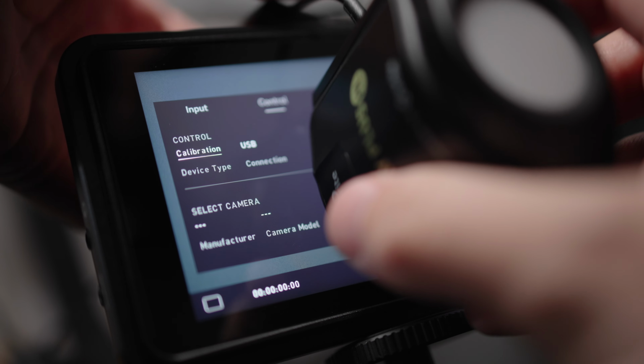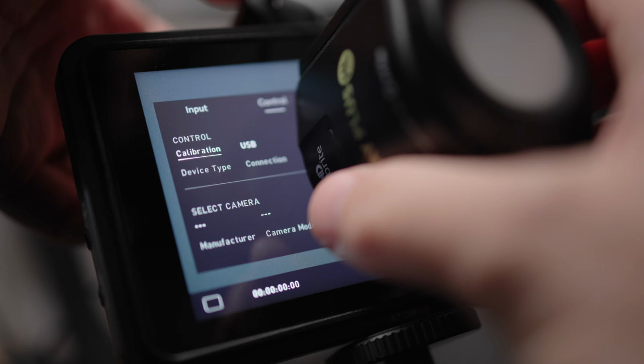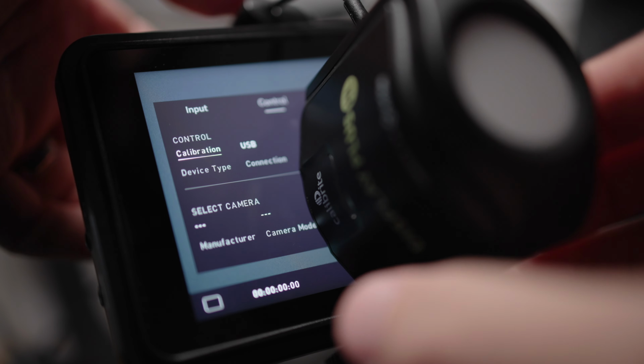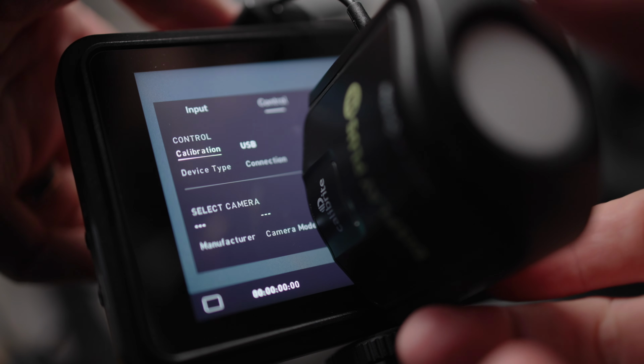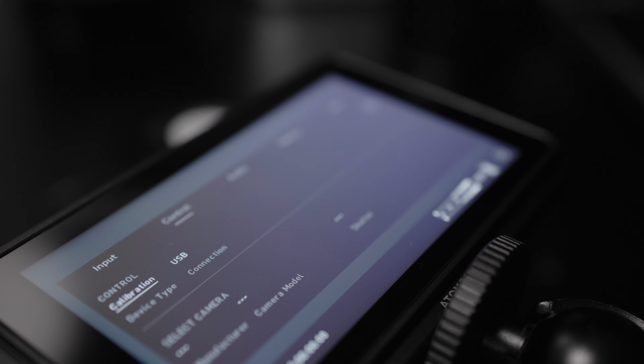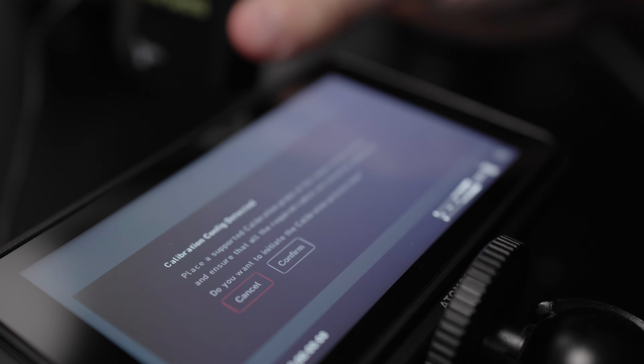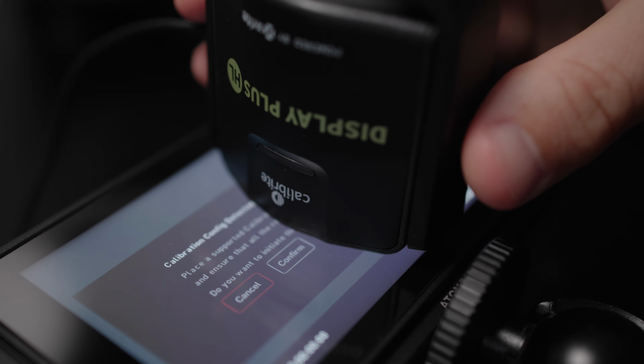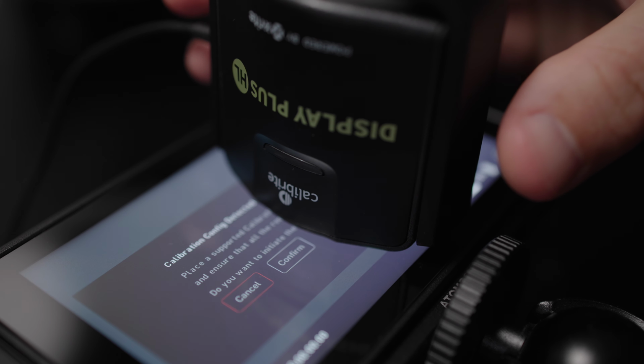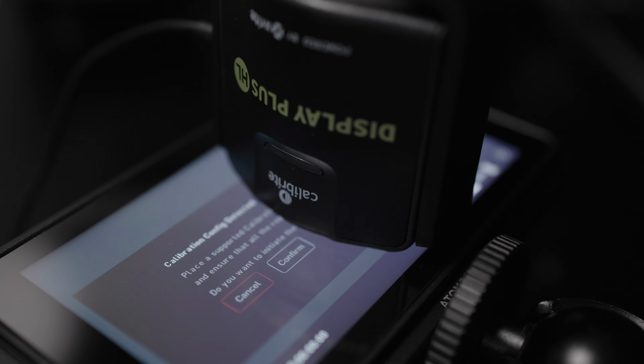As ever with these things, these probes can slip and slide around, so I'd recommend that you have it on a level, flat surface when you begin this process. Once you tap the calibration button, it will come up with a calibration config detected. So it will ask you to place a supported calibration probe at the center of the screen and ensure that all the required cables are securely connected. And then it will say, do you wish to initiate the calibration process now?